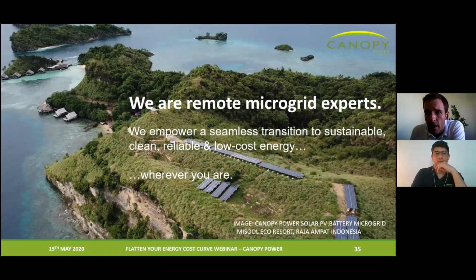So 100 meters by 100 meters of land. Quickly run through these. Depth of discharge considered for such projects, we typically run our batteries down to about 20% normally. It really depends on the battery and the recommendations of the supplier. Some are quite happy to go down to 0, but it depends how the manufacturer does their state of charge metrics. Sometimes when they say 0 state of charge, they actually have some left over anyway, so it's still safe.